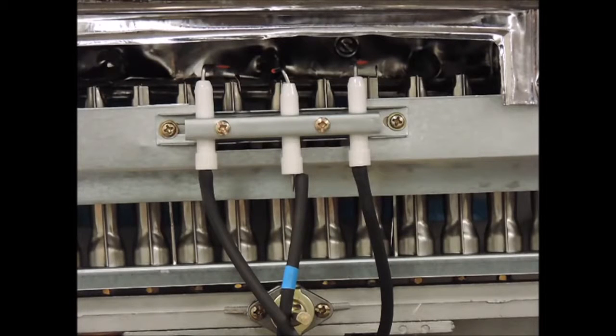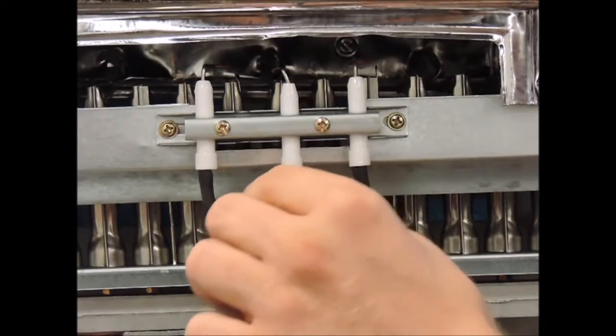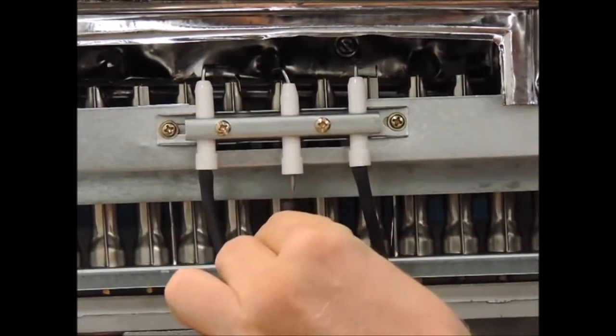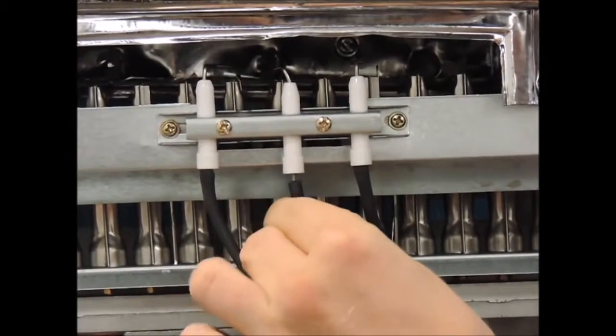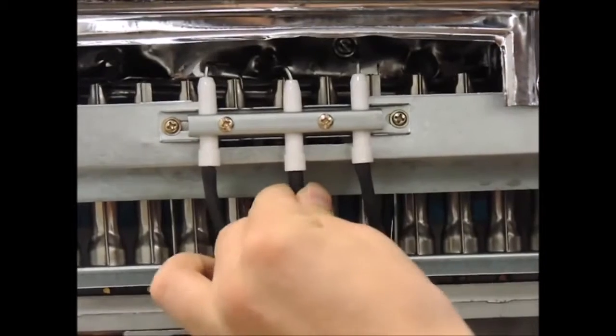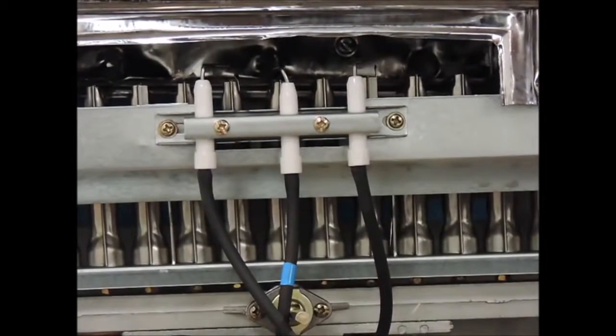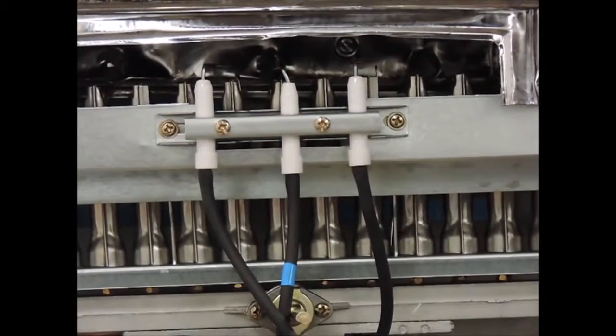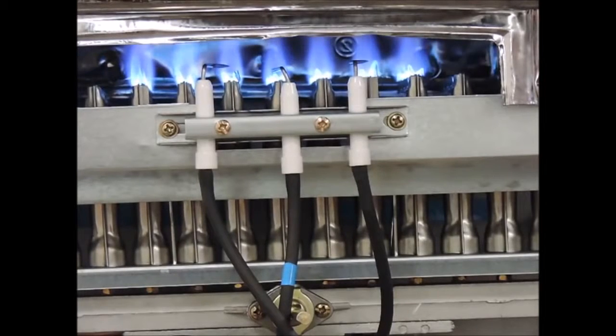If it is not, then you can pull the wire from the sensor and trim approximately 1/8 to a quarter inch off the tip of the wire and reconnect it to the sensor to give it a nice fresh connection. Another very distinctive behavior that indicates a bad connection to the thermocouple sensor is that while the flame is lit, the unit continues to click like it is trying to ignite.